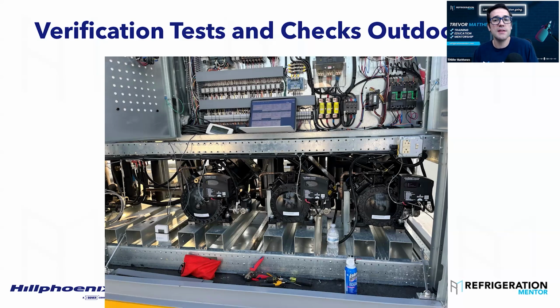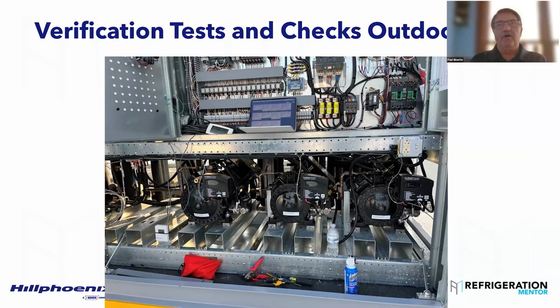So what are some of the things, this is an outdoor dry, what are some of the things that if a contractor called you a week before, you want them to have done? And I know you mentioned already, but it's good to go through it again. Yeah, I would actually have just a really quick 5-point checklist. Is the rack ready to run? It's under CO2 pressure. You did a pressure test.